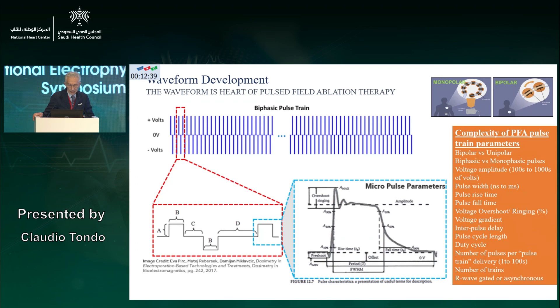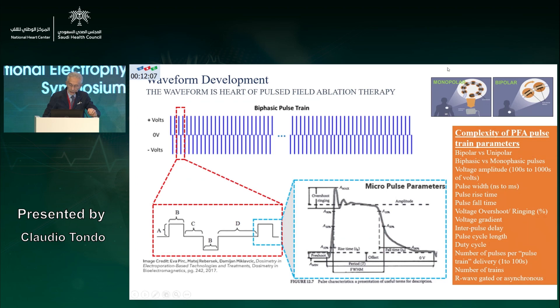Much time has been spent figuring out the best modality to apply electroporation. Currently, electroporation is applied using a biphasic pulse train, which determines the best electroporation effect on atrial tissue. You also have the option of monopolar or bipolar delivery, depending on catheter configuration. Different companies offer different modalities, but basically every PFA catheter uses a biphasic pulse train.